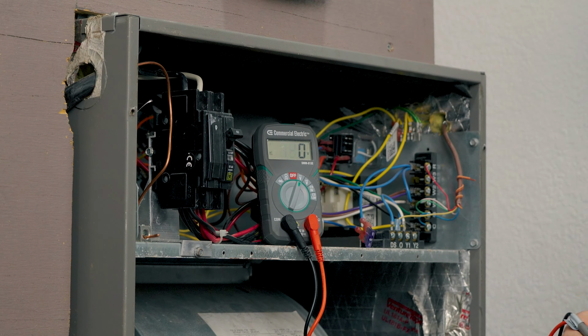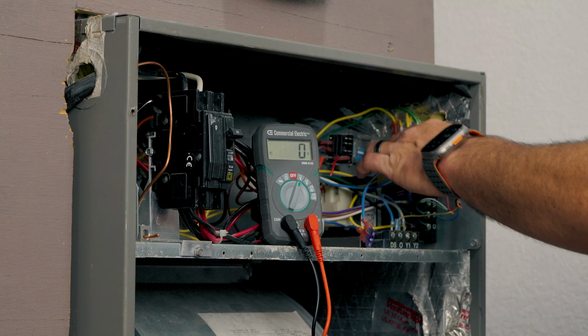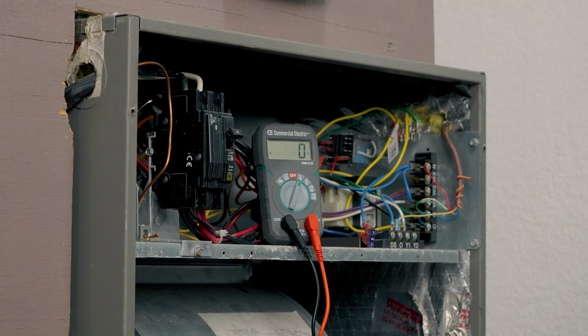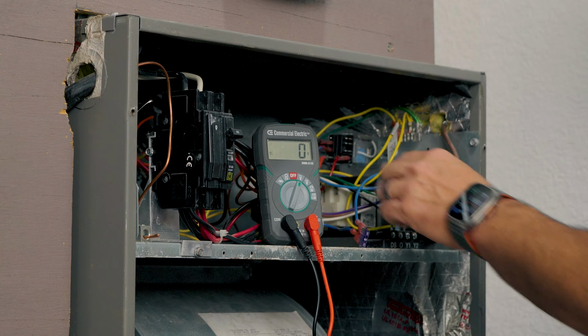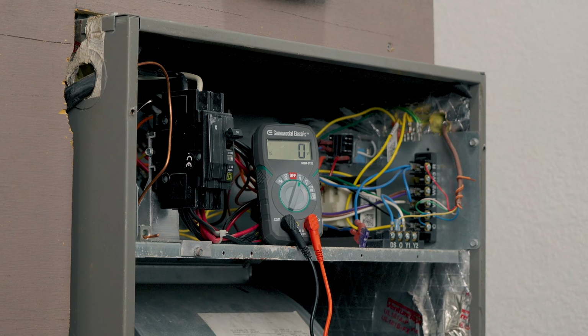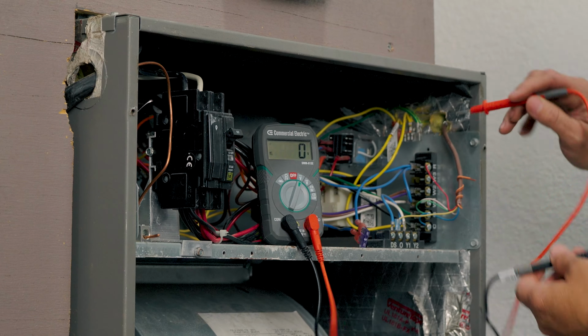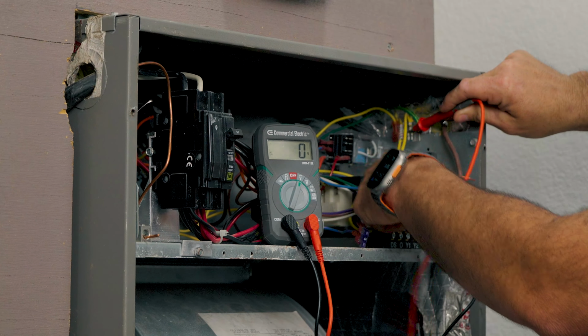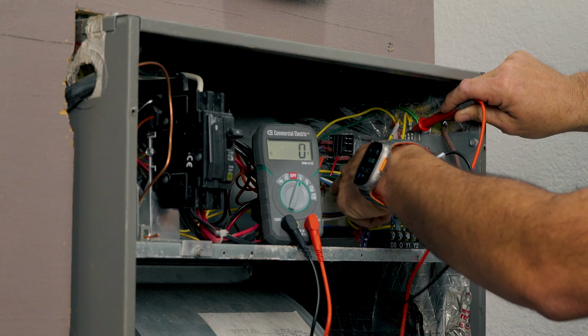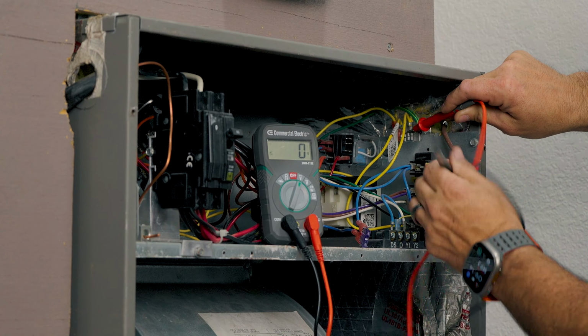The next thing we're going to check is our transformer. We're going to check to see that it's creating low voltage AC power. To test this, it's typically going to be a blue and a yellow wire, and we're going to look for between 21 to 28 volts. The yellow wire that comes off the transformer comes up to here, and the blue wire comes over to here.